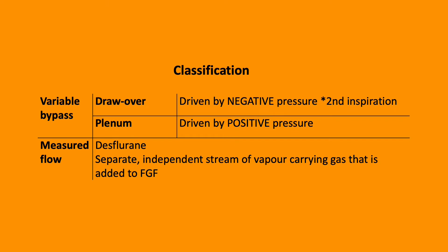Classification of vaporizers can be complex, but a common way is measured flow or variable bypass. Measured flow is for desflurane — there is a separate, independent stream of vaporizer flow which is added to the fresh gas flow. In comparison, variable bypass, the most common, is plenum. This is driven by a positive pressure due to the high resistance of the vaporizer.